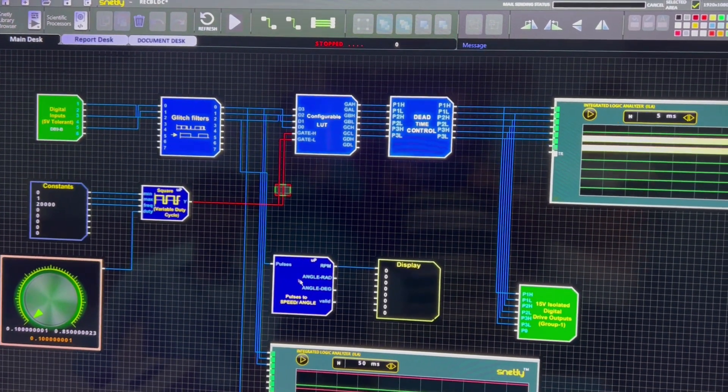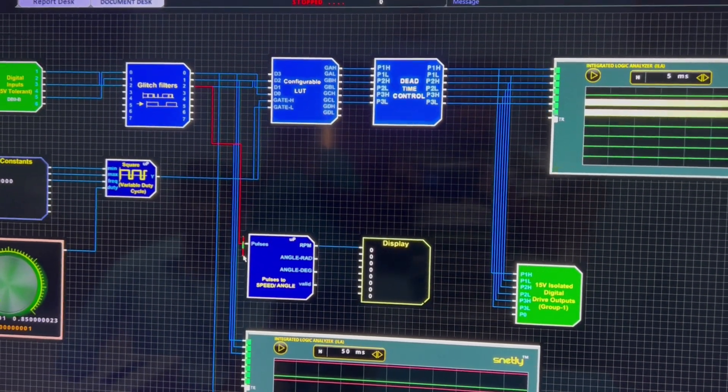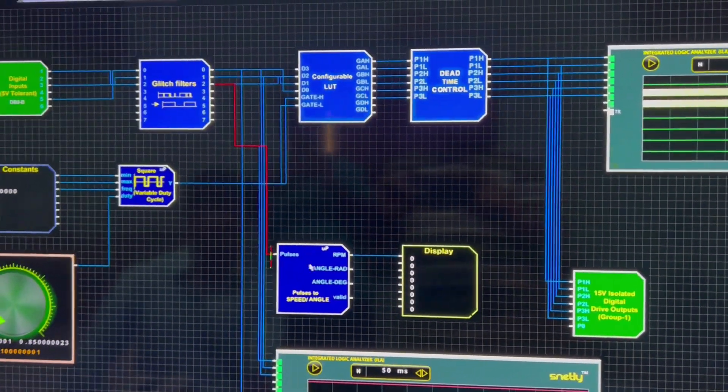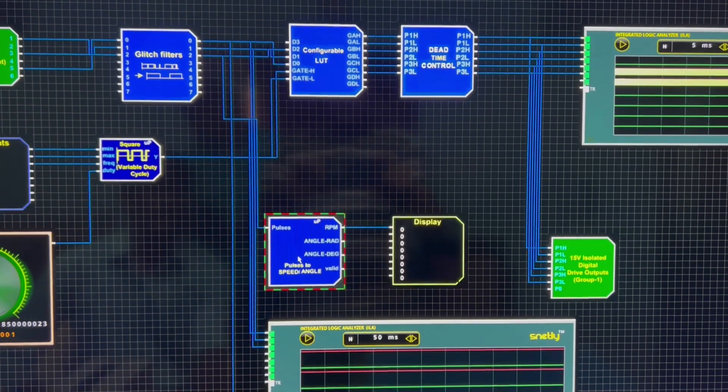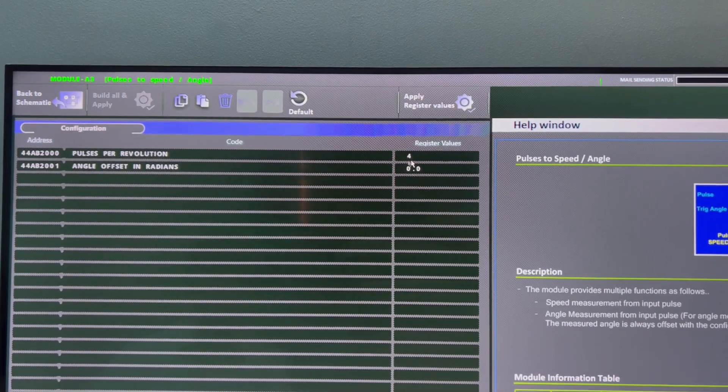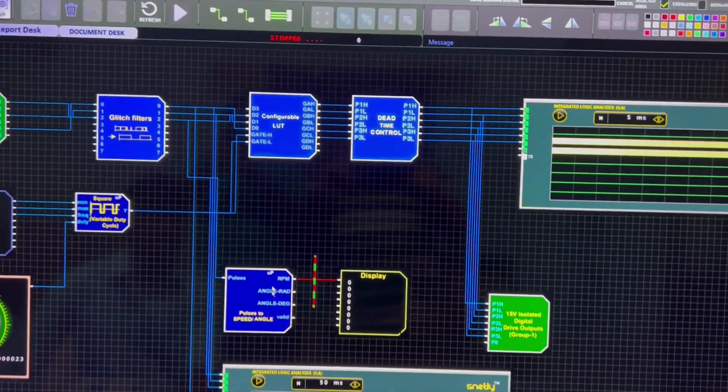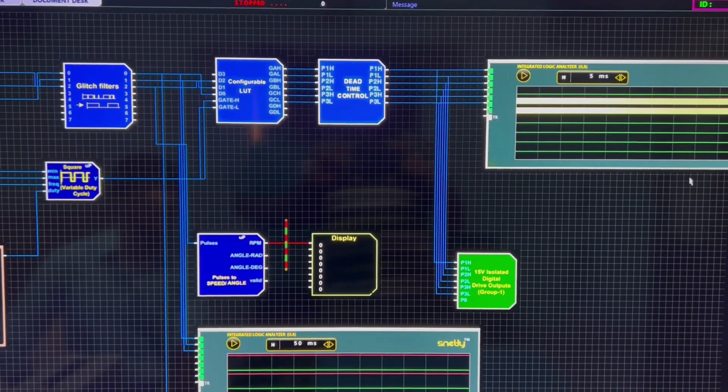For the speed measurement, we are using one of the speed feedback from the encoder. We need to configure the number of PPR in the motor. Here the number of PPR of this motor is 4, so we are configuring it to 4. Directly we are measuring the RPM, revolution per minute.